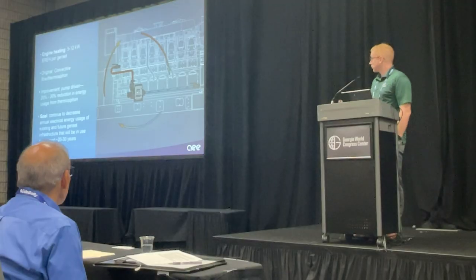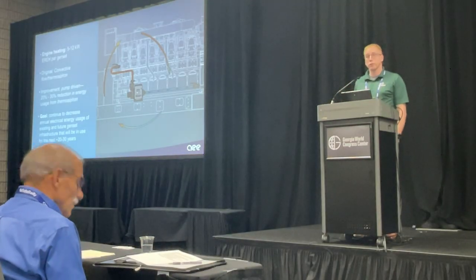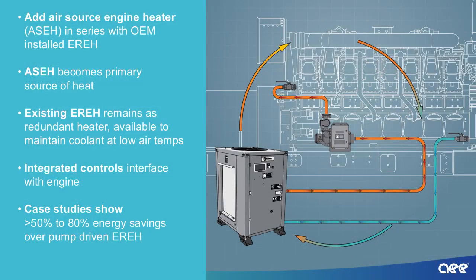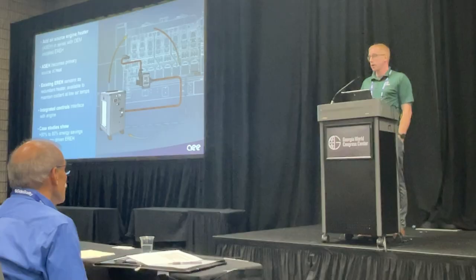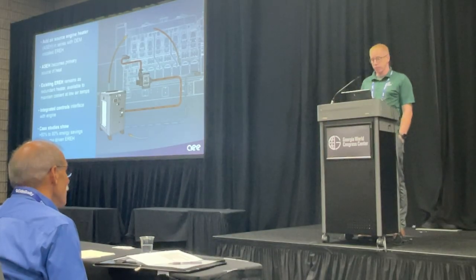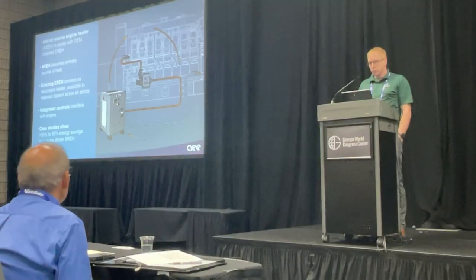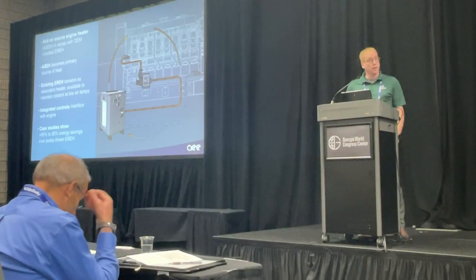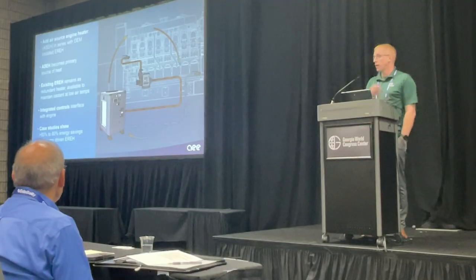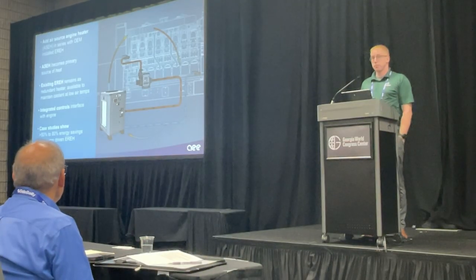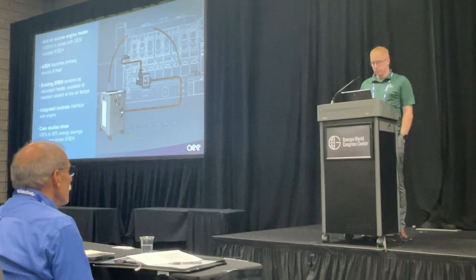What I'm talking about here is another way to decrease energy use further, by adding an air source engine heater, or air source heat pump, in series with the electric resistance heater. This maintains redundancy for installs or customers, so we're not replacing an OEM heater, we're adding something else. This becomes the primary heater, and the electric resistance heater is called upon by the air source engine heater as necessary when it gets colder and the COP of the air source unit is not adequate.